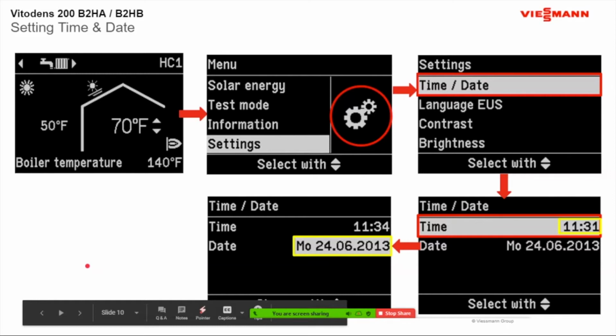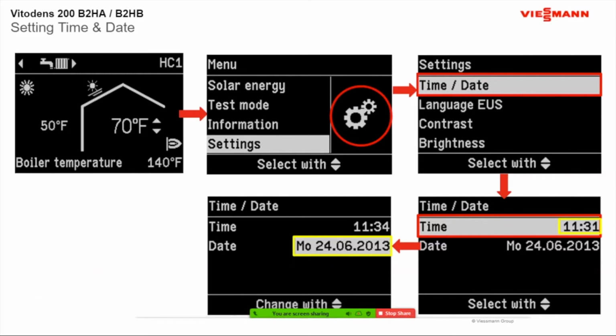I had one when I was younger and a manager of a company. We had replaced everything on the boiler, and by the time I got out of work and headed over to the place, it was about 7 o'clock at night. I had bought this Winter Watchman, which you tie into the boiler, and it gives you temperatures when it shuts off, voltage, and all of that. As I'm tying this in at 7, the lights dimmed in the house. I turned to the customer and asked, does this happen? He said, yep, every night at 7 o'clock. That would have helped me figure this out as well, because we could see that the boiler won't fire at 70 volts. That, to me, is why it's important to set your time and date.